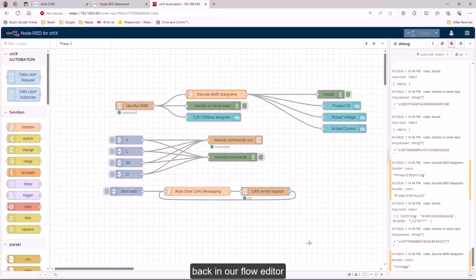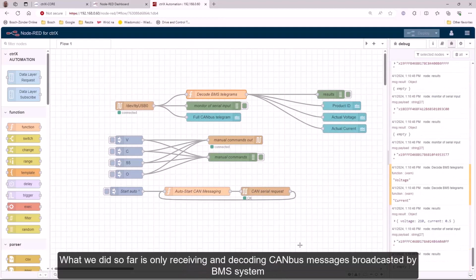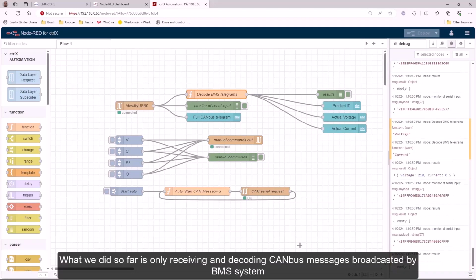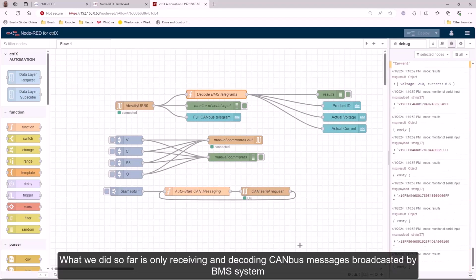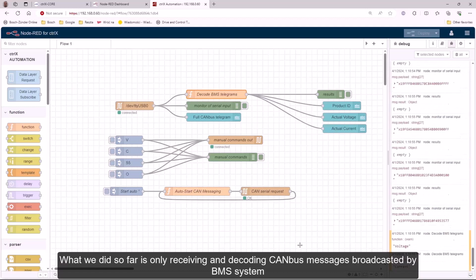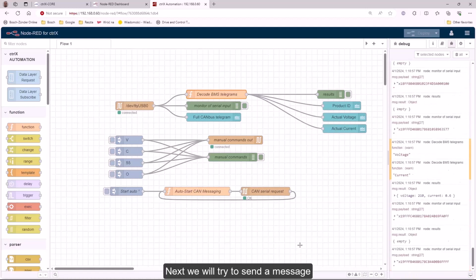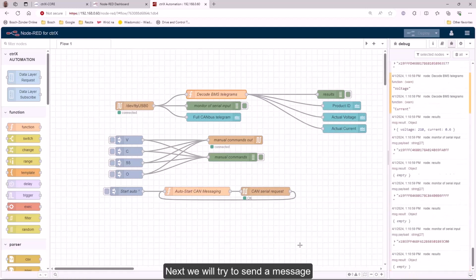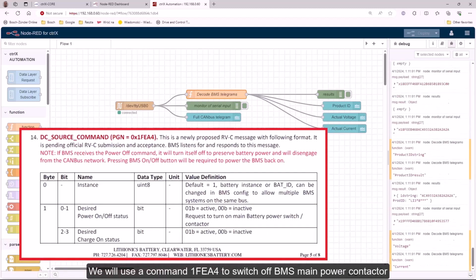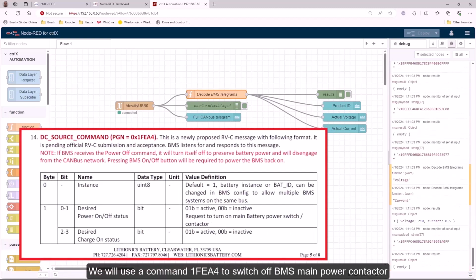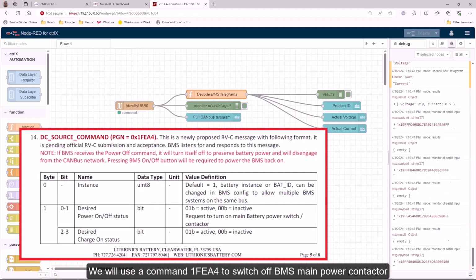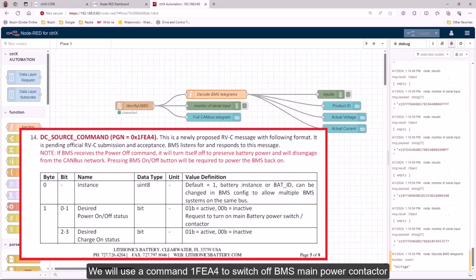Back in our flow editor, what we did so far is only receiving and decoding CANBUS messages broadcast by the BMS system. Next, we'll try to send a message. We'll use command 1FEA4 to switch off the BMS main power contactor.